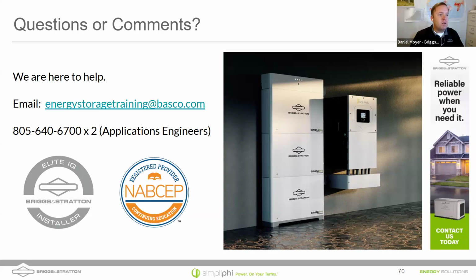Next question, Daniel. John's asking, do you have an outdoor battery storage solution? Well, the 6.6 battery can be installed outside, and if you're in a very cold climate where 14 degrees Fahrenheit is too high of a temperature for you, you need to charge when you're below zero, then we do have a heated battery enclosure option for the SimpliPHI batteries and the PHI batteries. Essentially we have heaters integrated into the BMS with temperature sensors that'll turn on when those batteries are cold. It's a little bit less efficient because you are using the batteries to keep the batteries warm. But those heaters are on a thermostatically controlled switch to allow them to heat the batteries only when needed. So yes, we do have options. Yeah, and somebody had mentioned that in the Q&A about cold weather considerations as well.